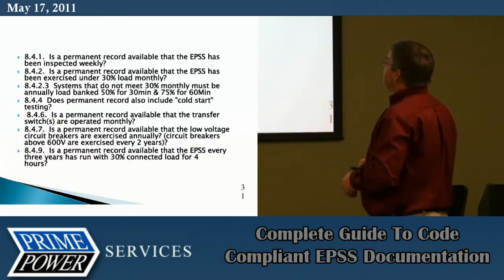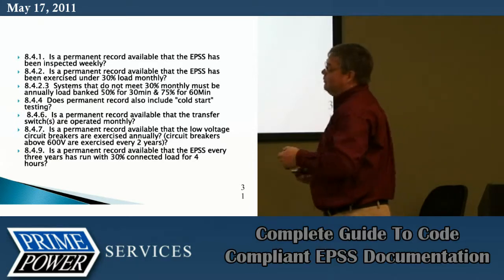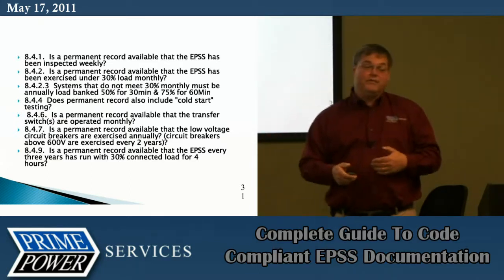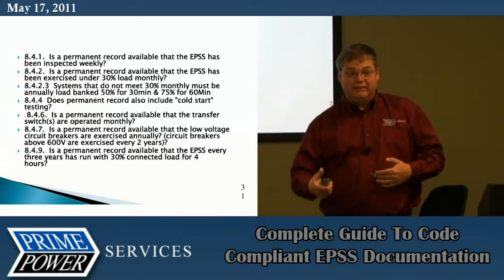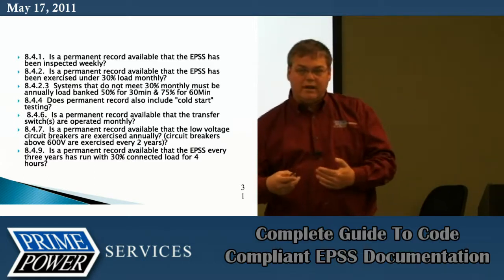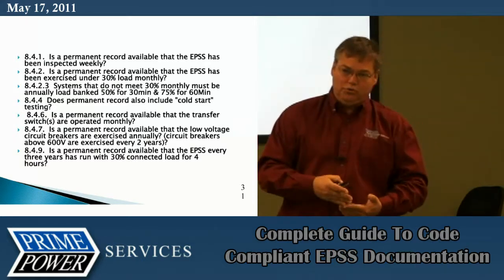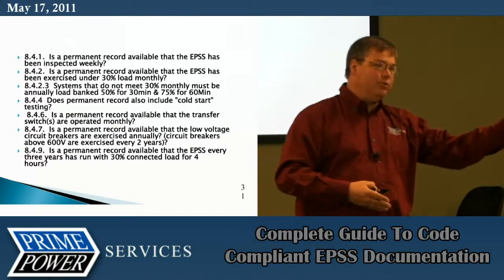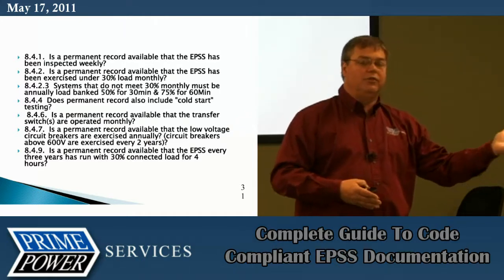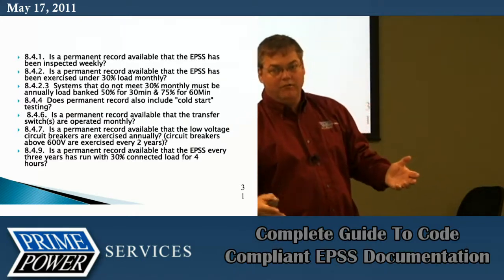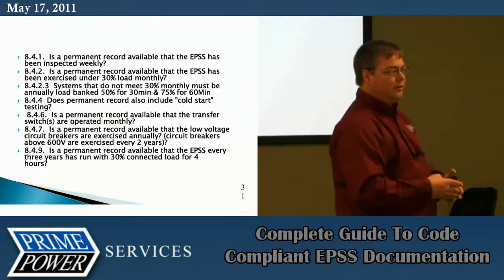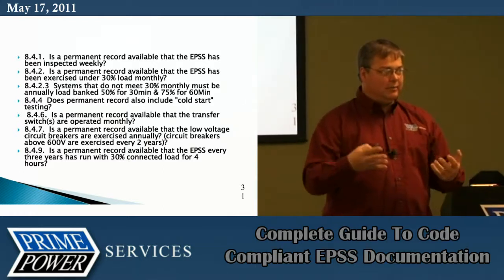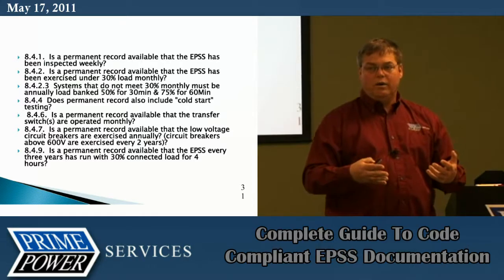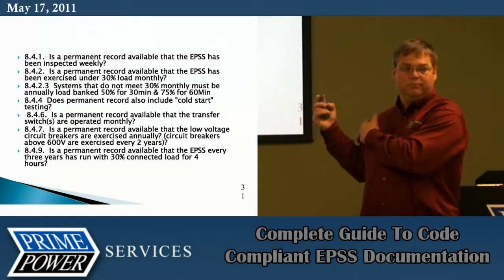All right, systems that do not meet 30%, this is where you get into the load bank. The standard says 25%, 50%, 75%. Word of advice: if you're going to use that annual load bank for your 4-hour test, or use that 4-hour test for that annual load bank, they supplement each other. What is wrong with this verbiage?